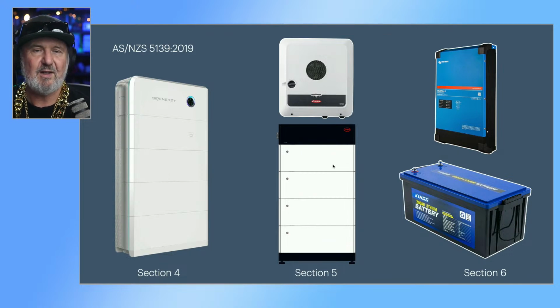It might have a bunch of IEC certificates, but unless it's listed, and in the case of Australia it's fairly easy to find out: the Clean Energy Council manage the approved product listing, and that means they have confirmed that the product is appropriate for Sections 4 or 5. And if it's not in 4 or 5, it won't be on their list. Section 6 is deemed to be of somewhat unknown.